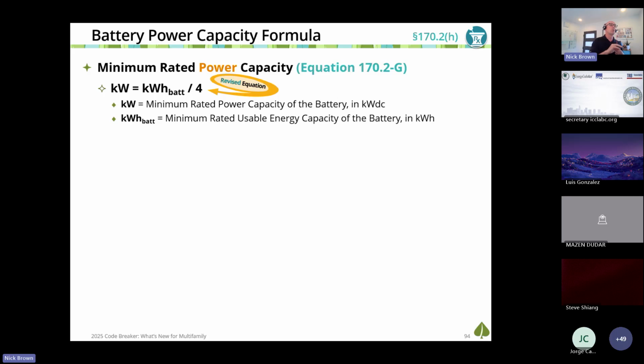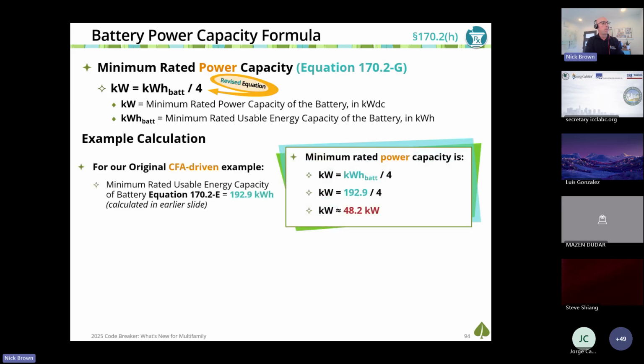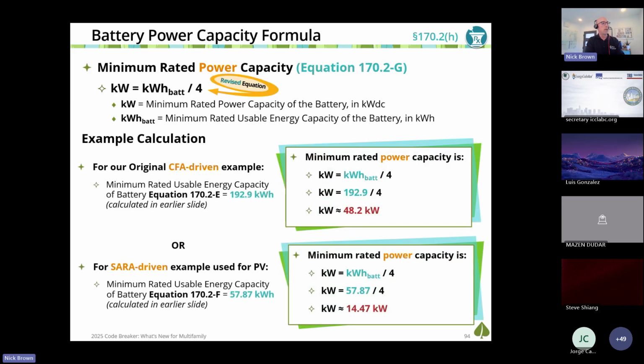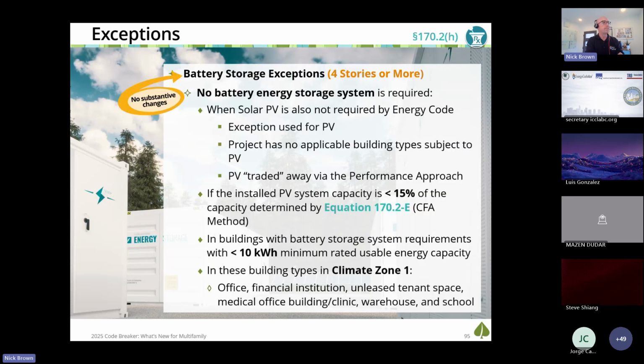And this changed too. This was a more complicated equation last code cycle. Now you just take the energy capacity of the battery measured in kWh, divide it by 4, and you get the power capacity of the battery. So for that 193 kilowatt hour battery, works out to 48. For that 58 kilowatt hour battery, it works out to 14.5.